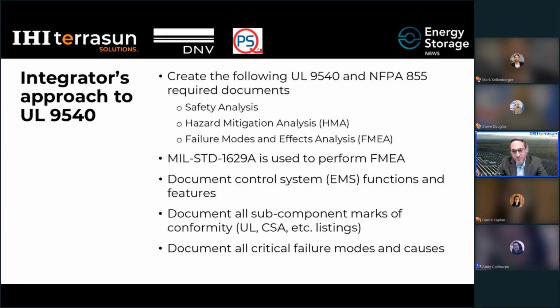At TerraSun, when we create these documents, we follow military standard 1629 alpha for creating our failure modes effects analysis. What goes into the safety analysis is a very thorough and detailed description of the control system, its features and functions. We document all of the subcomponents of the system to ensure that they have either been tested already by a national lab or will go through testing as part of the UL 9540 field evaluation. We also must document critical failure modes and causes to be able to prove to local authorities having jurisdiction that the system will perform safely and that the systems that are designed for those safety features have been thoroughly tested.